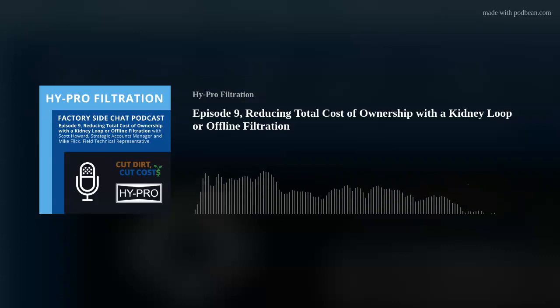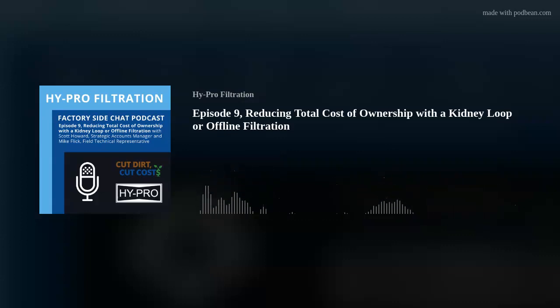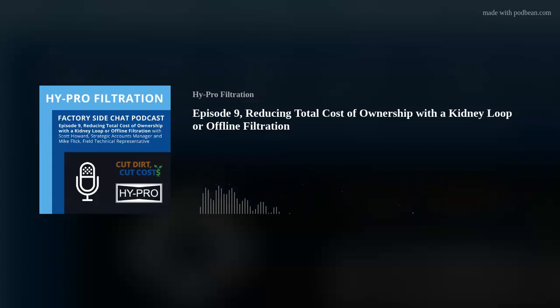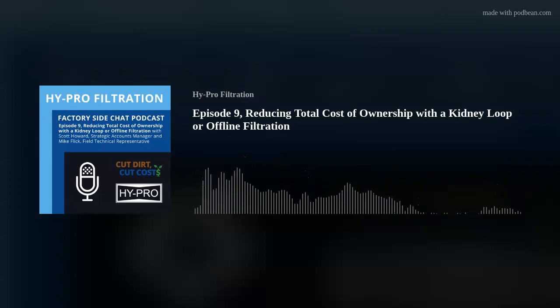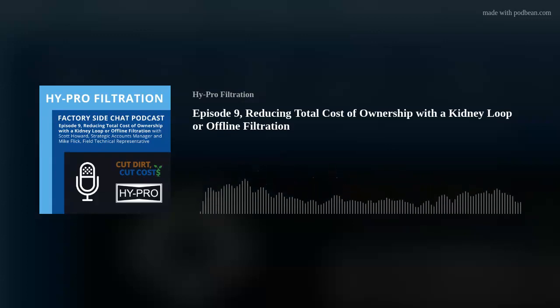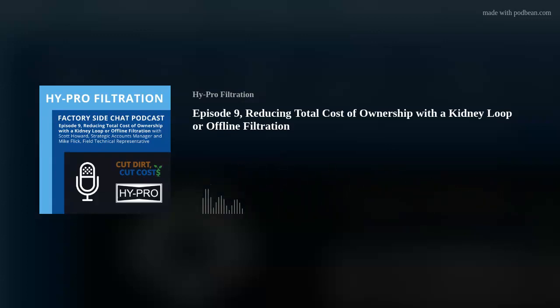So that is correct. The kidney loop that you're referring to, the way I like to look at it is it becomes the workhorse of your system. And when the kidney loop becomes your workhorse, like you mentioned, you're using a lower micron filter, which is polishing your oil on a repetitive basis. And when that's happening, your other filters are now becoming, as I like to look at them, guardians or protectors. So your pressure filter that is sending oil downstream is basically just there to polish things even further and catch any debris that somehow may have gotten into the tank or what have you.